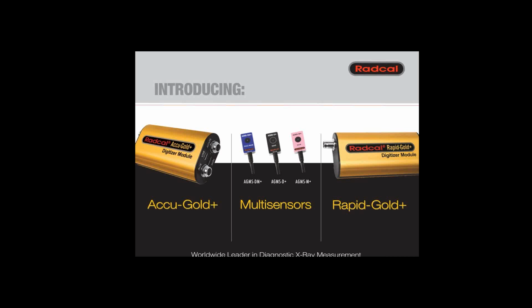The single-target stacked sensors, multi-sensors, are available in diagnostic, mammo, or the diagnostic plus mammo sensors for an all-in-one fashion. The single target eliminates heel effect and errors in positioning the sensor. The Multi-Sensor Plus is the smallest footprint multi-sensor available on the market today, and its calibration stays with each sensor, so they are truly interchangeable among other Accu-Gold-based systems.